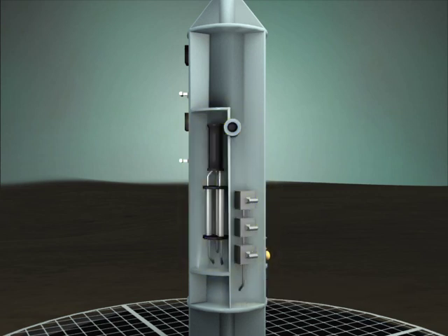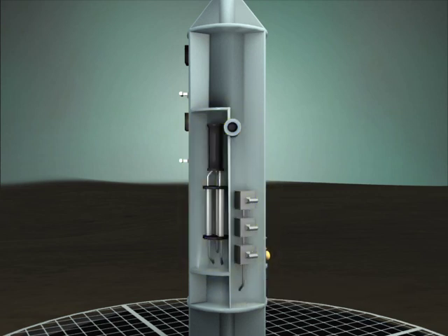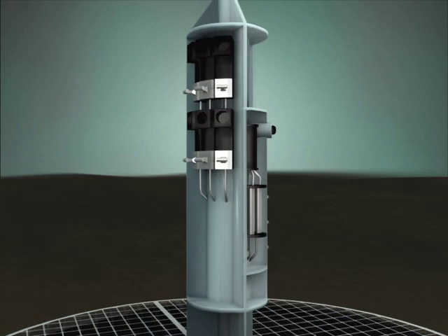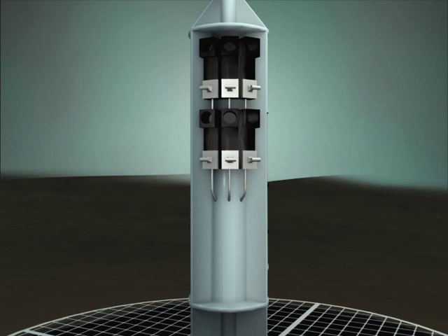A pressure bay contains highly sensitive gauges, batteries, and a computer that makes measurements and stores data for up to six years. A long-term fluid sampling bay contains samplers that collect fluids from depth using an osmotic pump, storing the samples in thin tubes for years until they can be recovered and analyzed on shore.